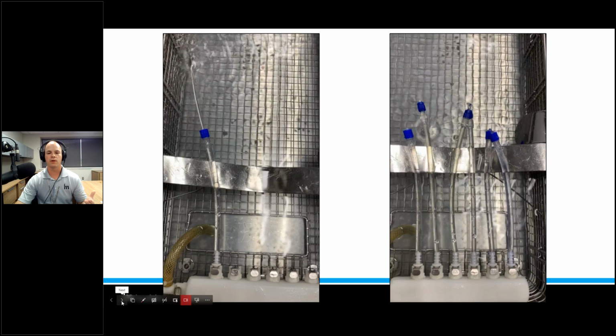All right, so the more instruments we hook up in this particular unit, and I would suggest it's probably consistent across all ultrasonic units that have this capability, you're going to lose some water pressure. Hopefully losing water pressure doesn't diminish the cleaning ability of it, but in this case it probably would, because there's barely any water going through. But that's why you test. If you're doing an ultrasonic cleaner that has 32 hookups, hooking up all 32 of them is going to diminish the flow through the system. All right, so that's just something to be aware of when it comes to testing and also real life application.